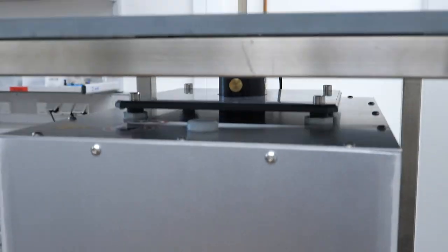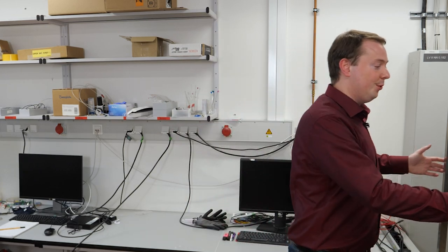We're back in the construction lab, and the true benefits of signal-enhanced contrast agents will be revealed here. Because we've seen so far that these contrast agents can be used in standard magnetic resonance tomography, which is usually not very portable, it needs to have stationary devices, but with this signal enhancement, we have less demands on the magnet technology. So all we need is, first of all, a device that produces our contrast agents, and this can be perfectly put on wheels. This is what I'm going to show you right here.